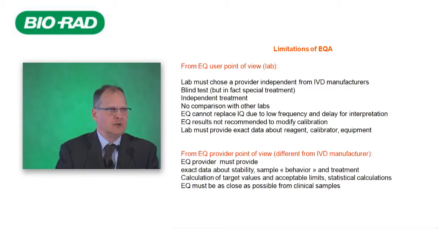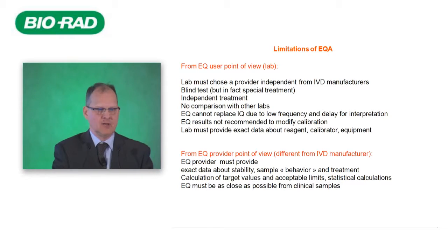There are some limitations of EQA from the user and also from the manufacturers. From the user, the lab must choose a provider independent of in vitro diagnostic manufacturers. This is not always possible. We must remember that we realize blind tests, but in fact, we all know that a quality control is different from a patient sample, even with the presentation of the kind of sample. We must have an independent treatment and no help or comparison with your neighbor or other labs. EQA cannot replace internal calibration and internal quality control due to the low frequency of those tests and the delay for interpretation. And finally, EQA result is not recommended to modify calibration, and a lab must provide exact data in order to have exact peer values, regarding reagent, calibrator, and equipment.